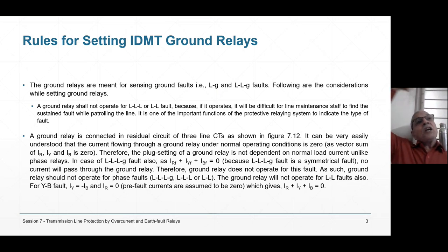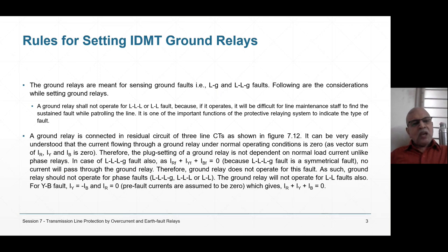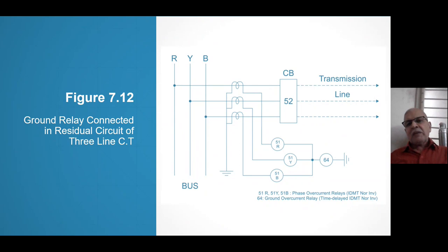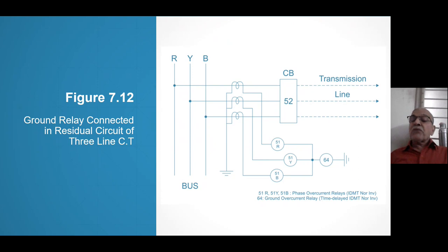The first rule: in phase relays, the relay is set beyond the rated current of the equipment on the line. But for the ground relay that is not true. This is a three-line diagram with R, Y, B buses and a transmission line. We have IDMT overcurrent relays 51R, 51Y, 51B for the line, and relay 64 is the ground relay whose setting rule we need to decide.